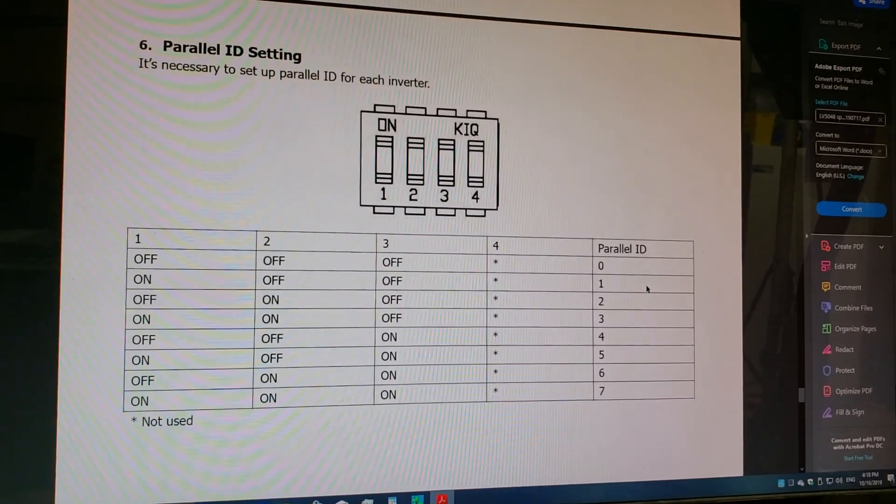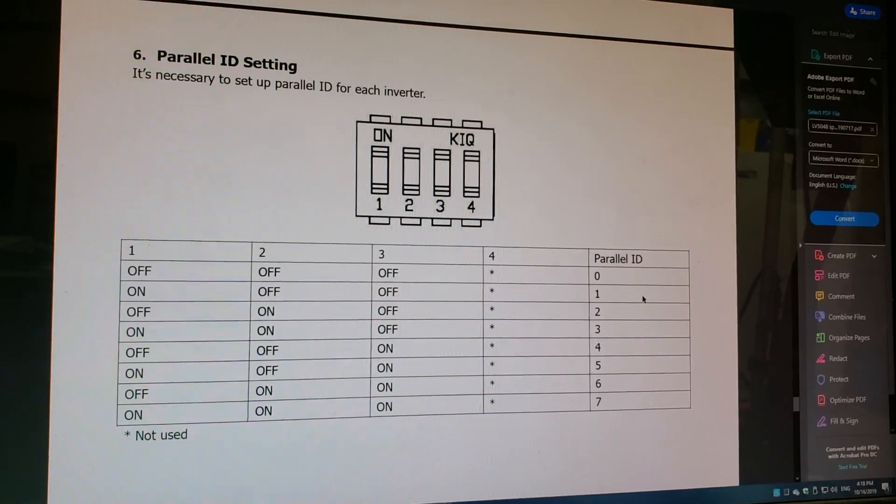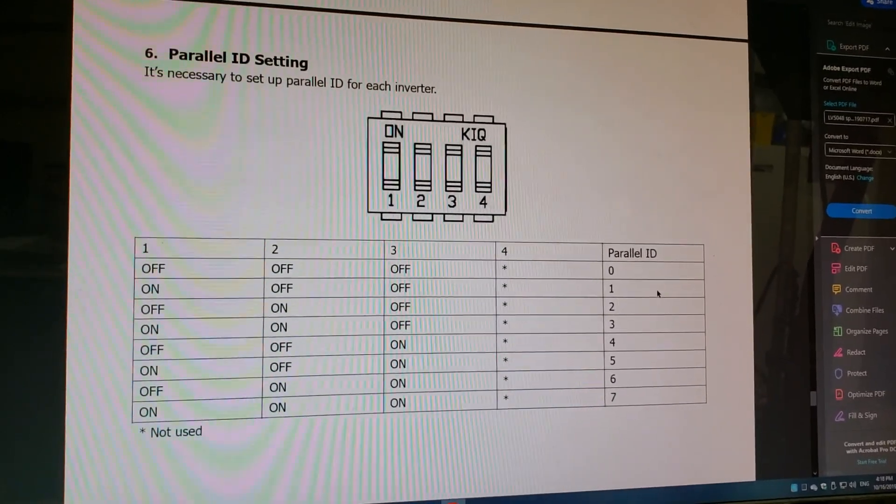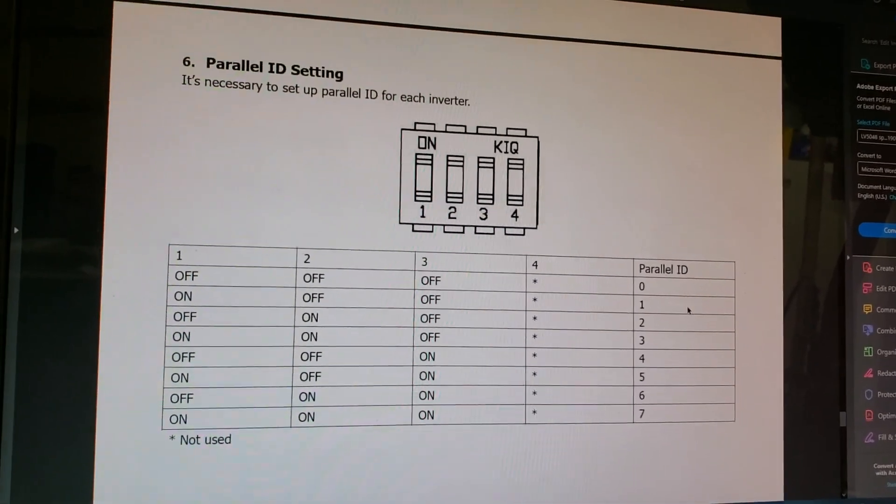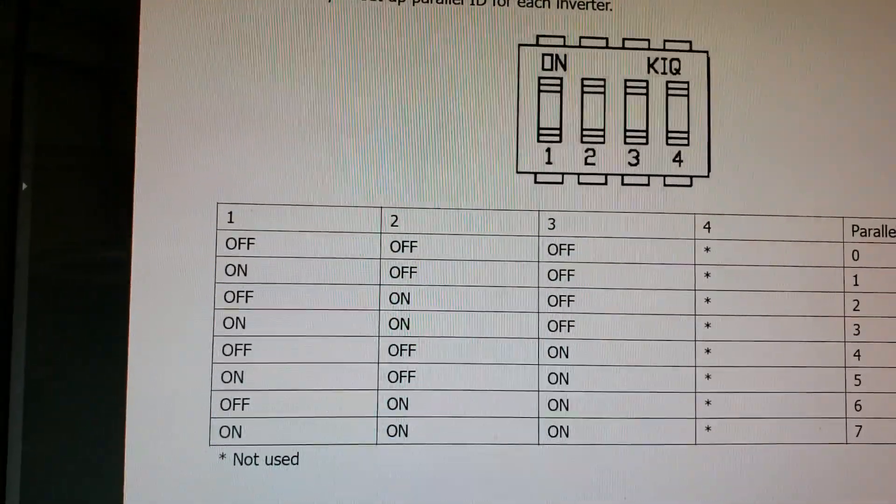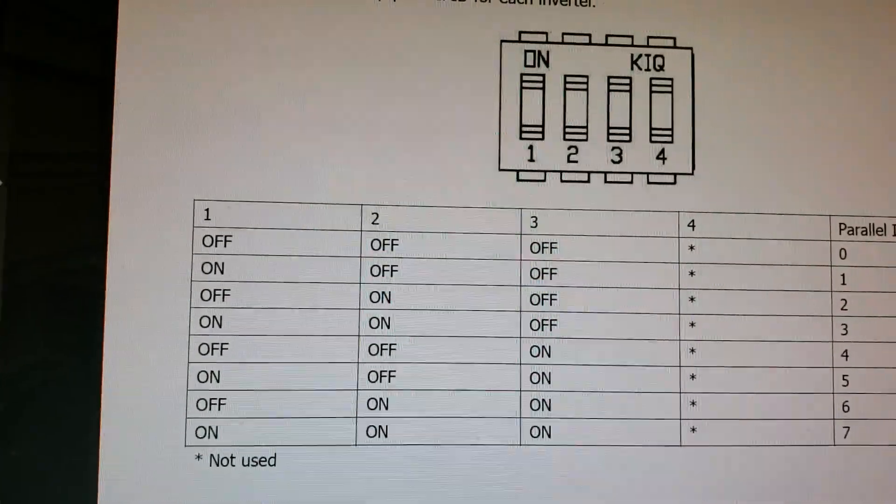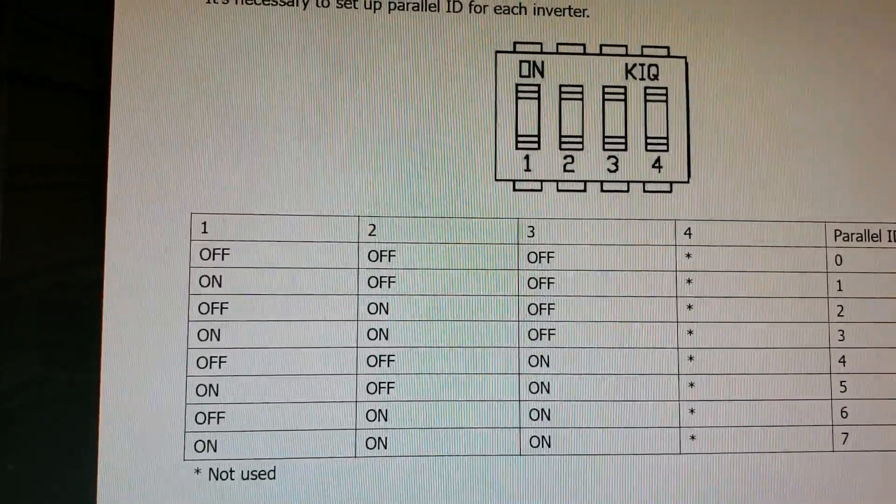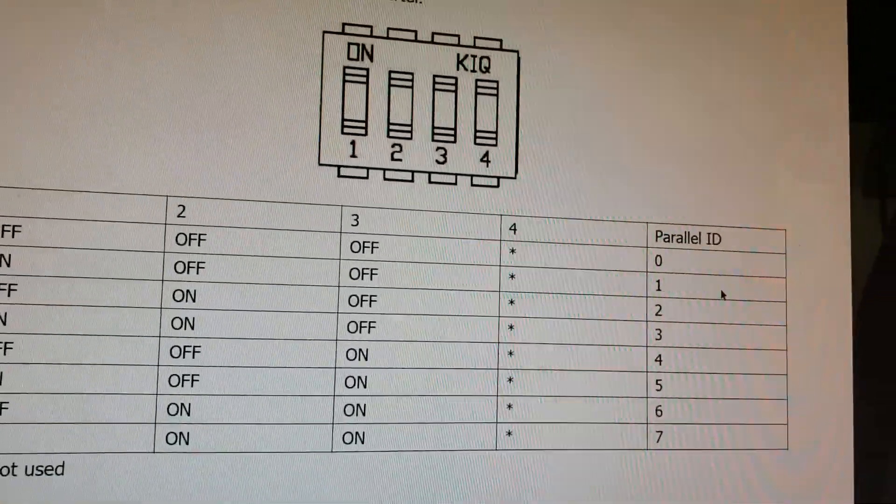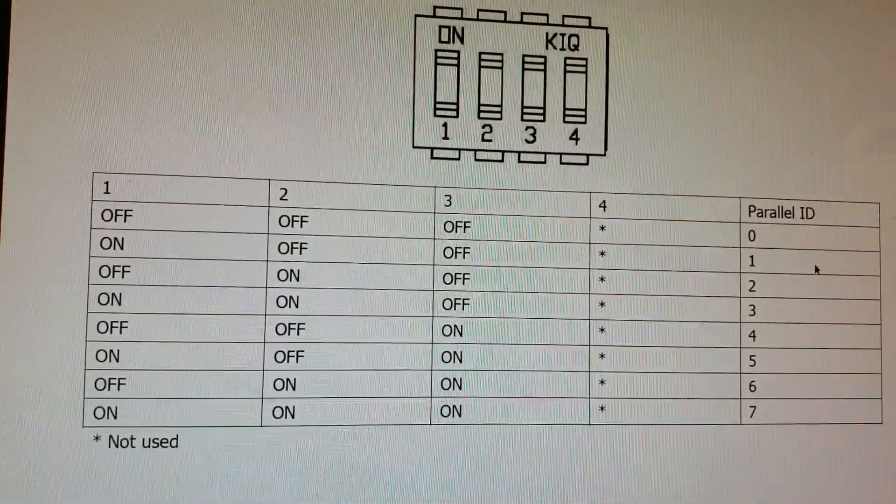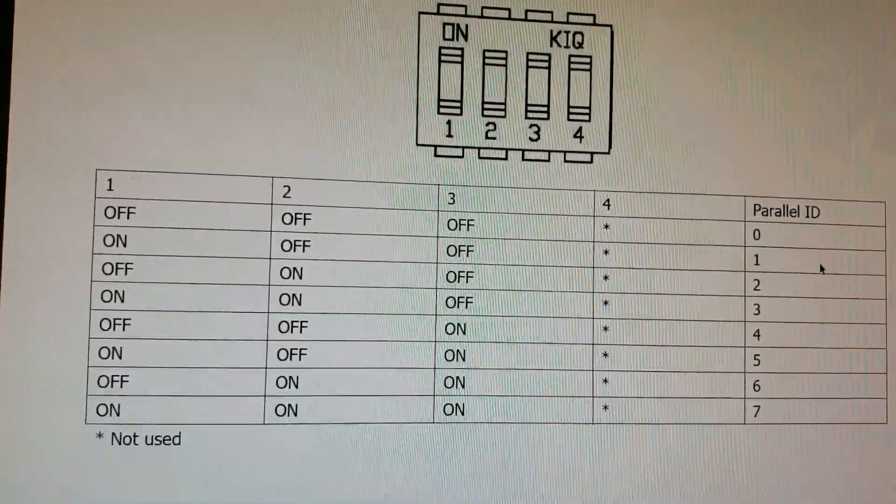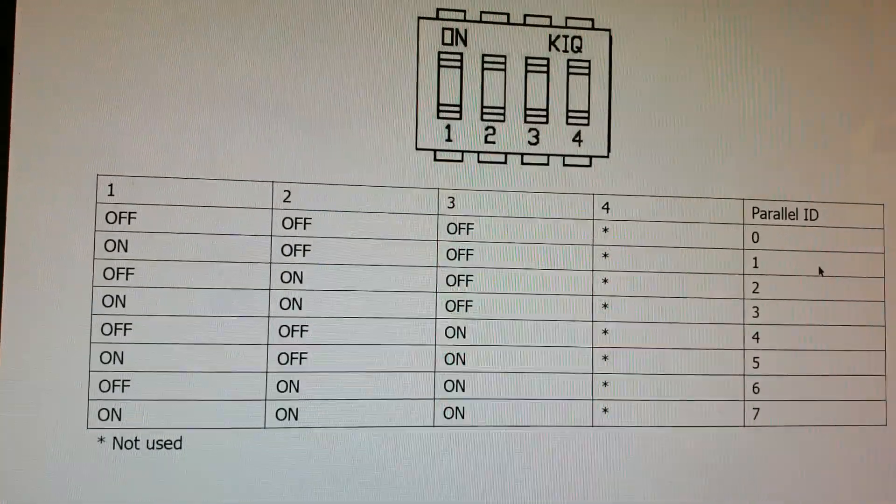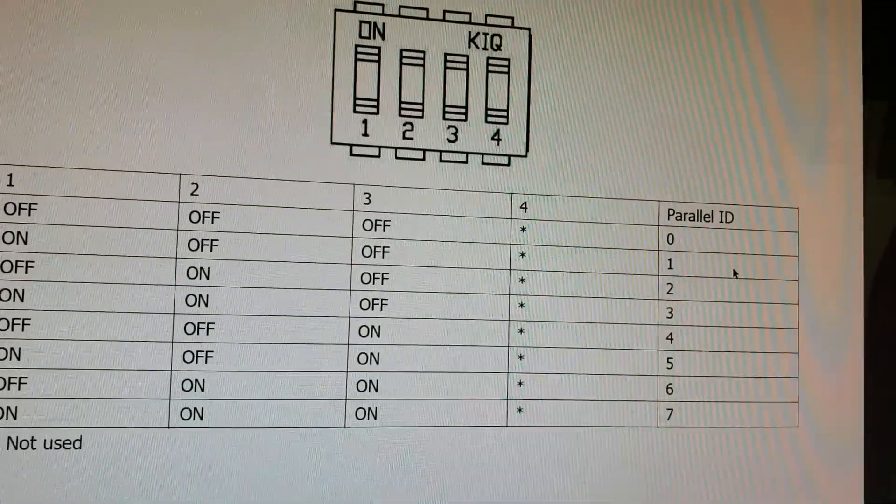In addition to necessary connections between two inverters, parallel ID must be set on each inverter. Let's look at this diagram in the owner's manual. I set up my inverter one on the DIP switches - I left them all off. So one, two, and three I left in the off position for a parallel ID of zero. For unit number two, I turned the first switch to the on position, left the other two off, and of course number four is not being used and it's left in the off position for a parallel ID of one.